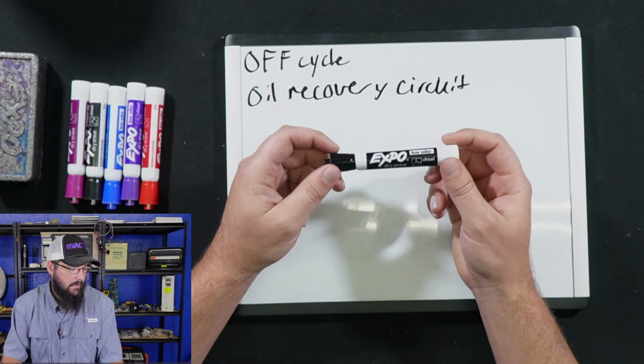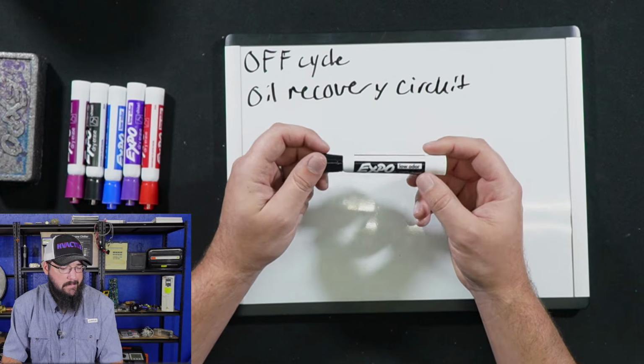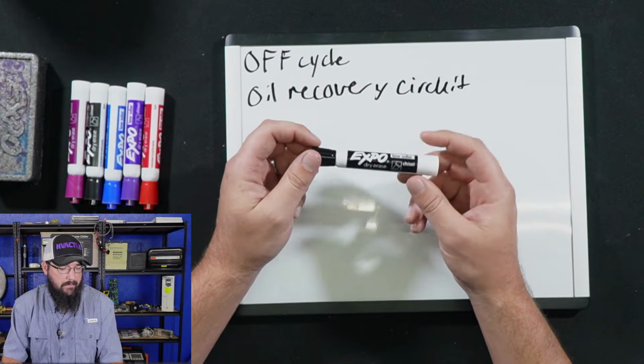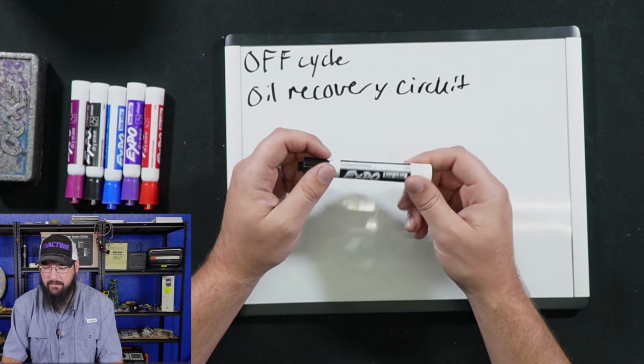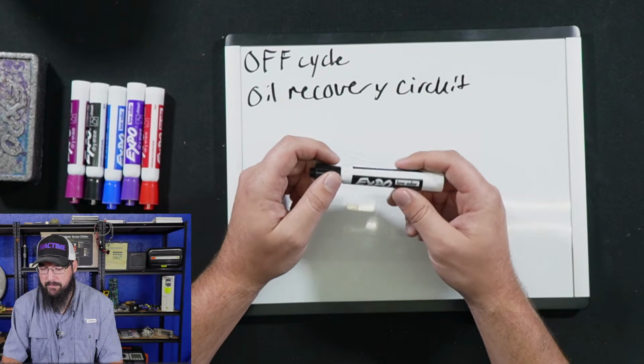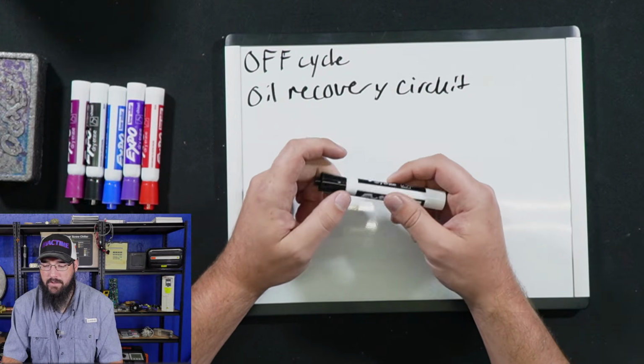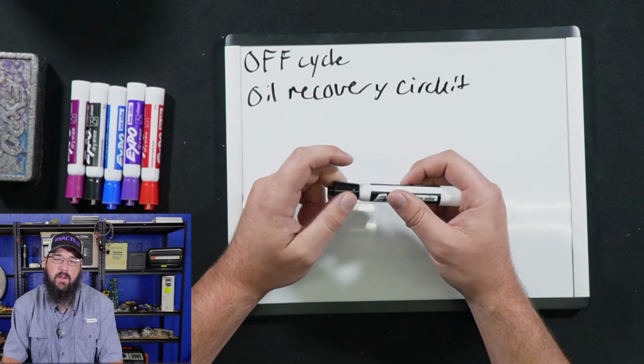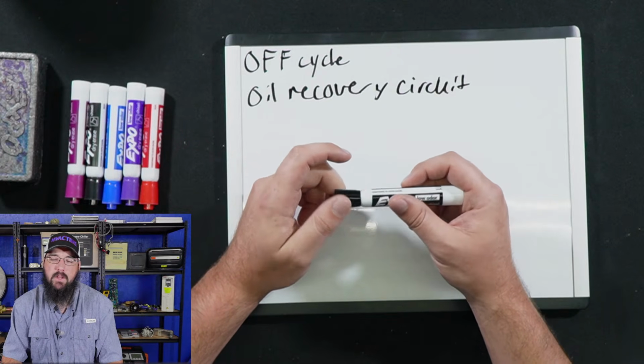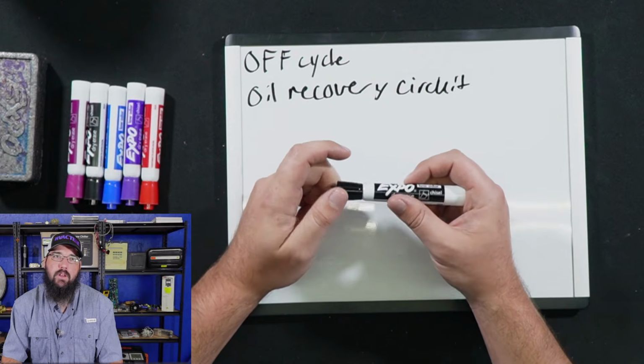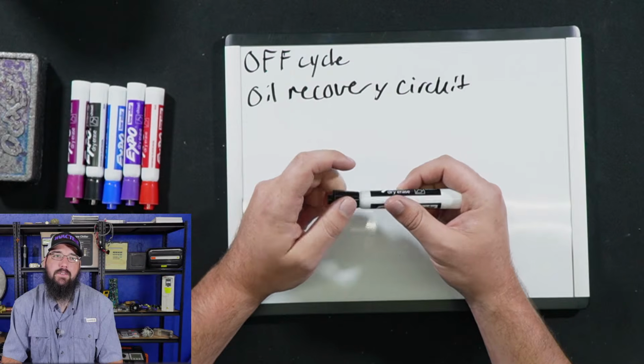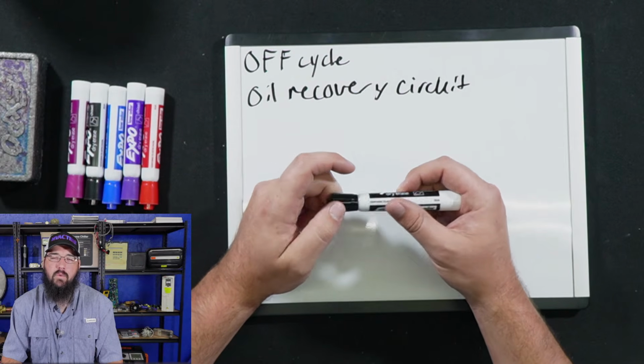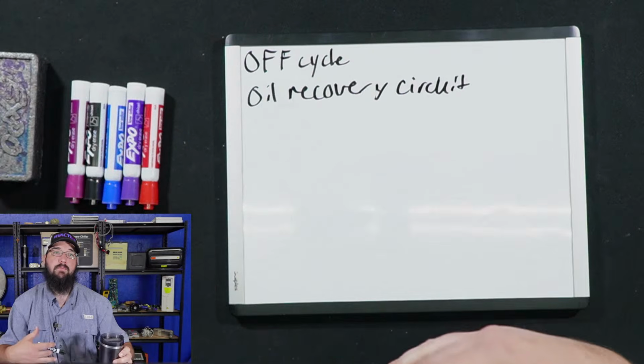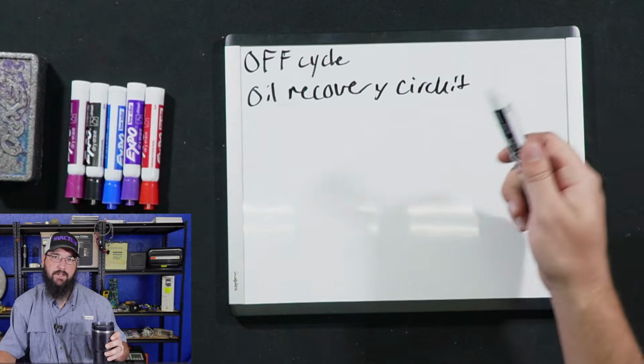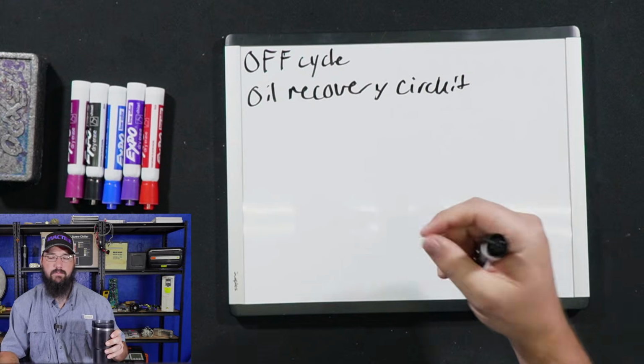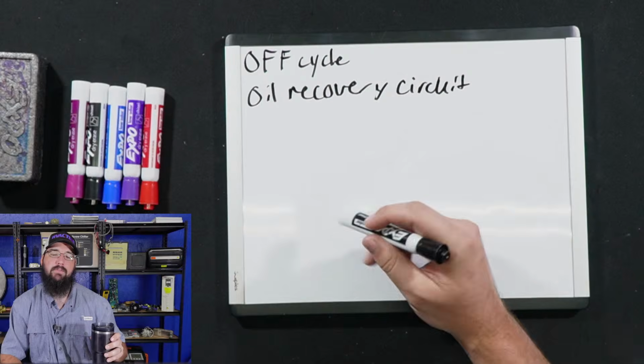So, yeah, we have to have enough differential between the circuits. That's one of the issues with running too cold of condenser water on a water-cooled system. You can get the DP too low if you're not careful, and that low DP will result in oil migration. Like that will be the failure. And that's if you don't push it into a choke condition, depending on your load, because you just don't have enough lift in order to maintain the mass flow.